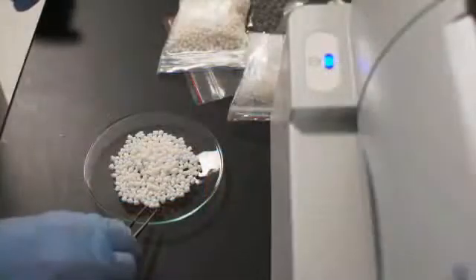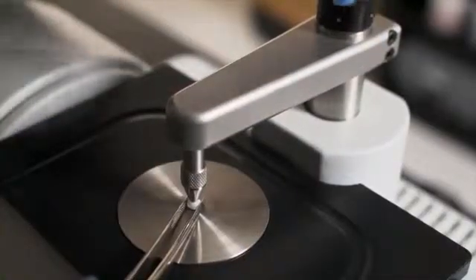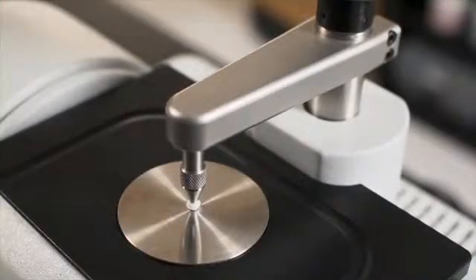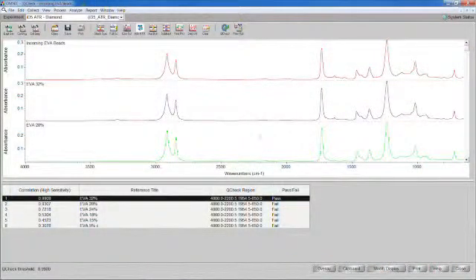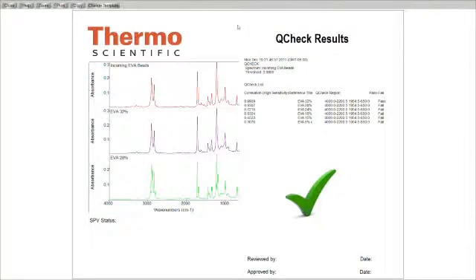For example, with the Nicolet IS-5, you don't need to be a trained spectroscopist to verify incoming material formulations. In just a few seconds, a spectrum is created, and the OMNIC Q-Check routine determines whether the material meets specification.